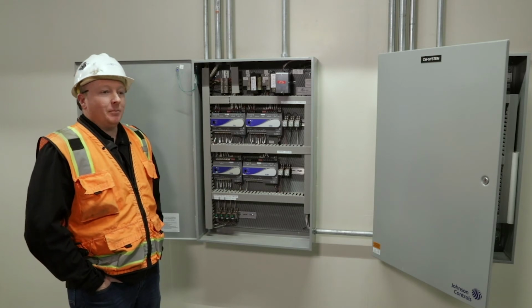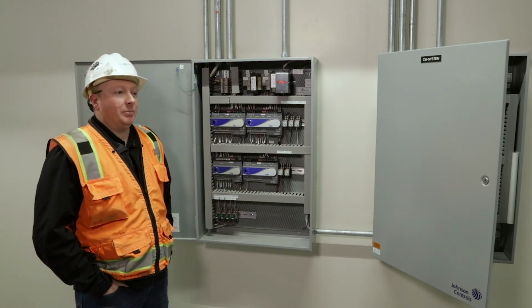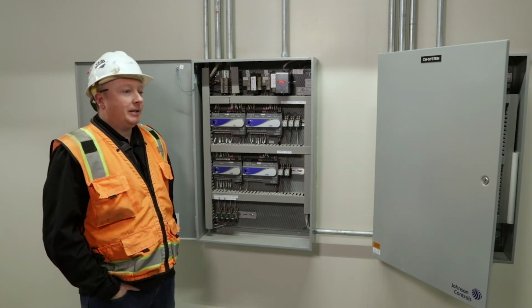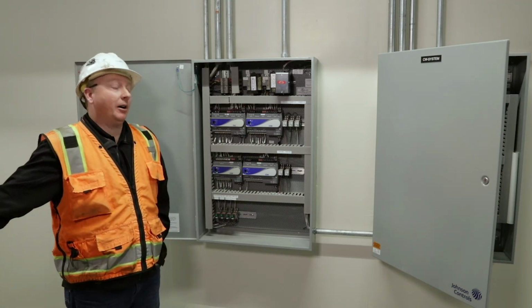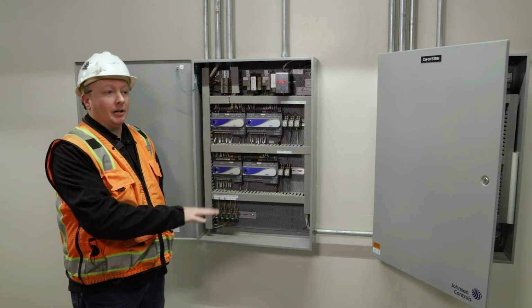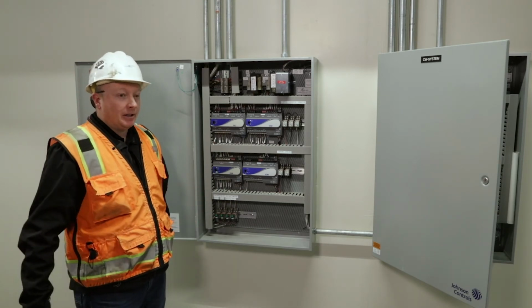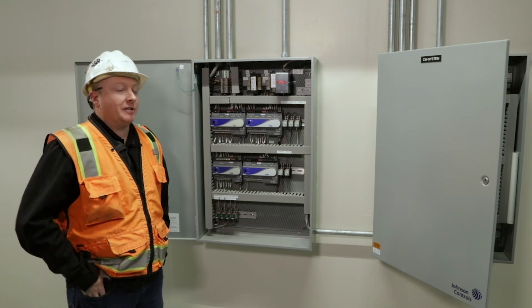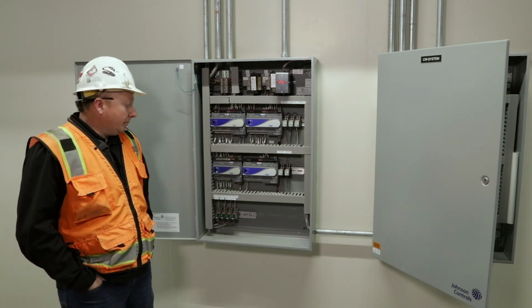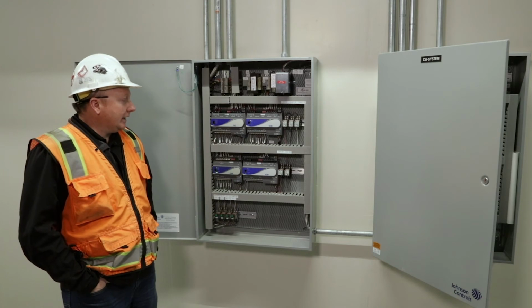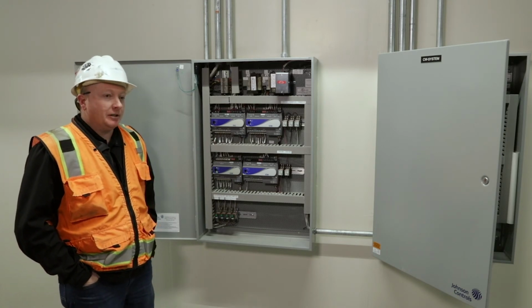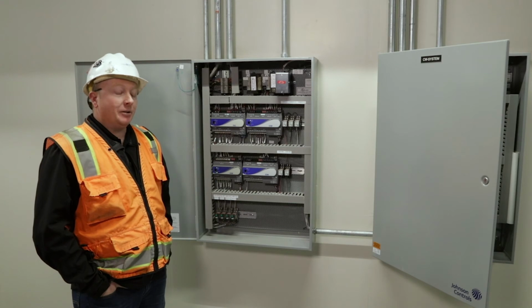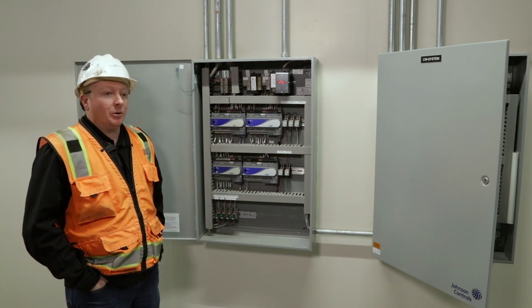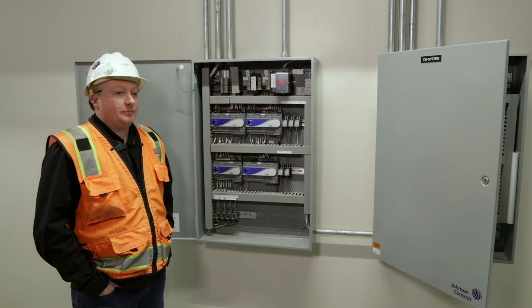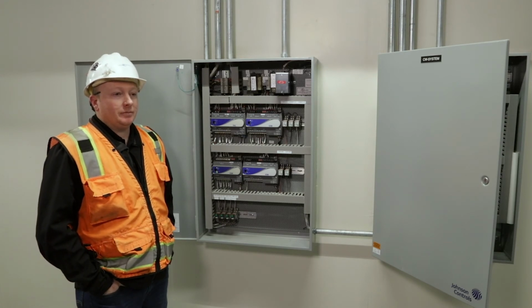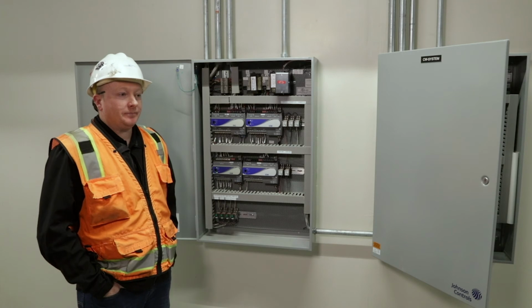And that's the same control strategy for your boiler system too. So basically 2 parallel pumps that control for DP. That DP sensor is hardwired from air handler 4 all the way up to the controller. We're not using the network to share the information. So we should have good, reliable control as long as that sensor is working. Trying to think if there's anything else. I think that's pretty much it, unless you guys have any questions. There's a lot of stuff I'm kind of just brushing over real quick. So hit me with questions if you've got them.